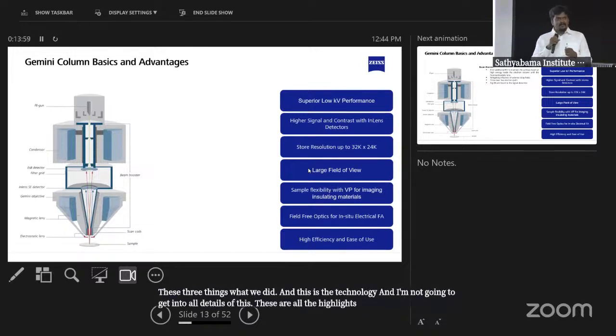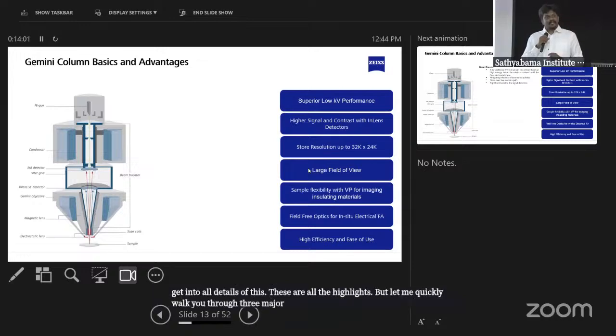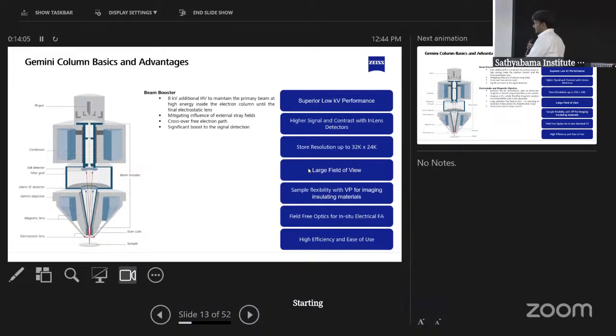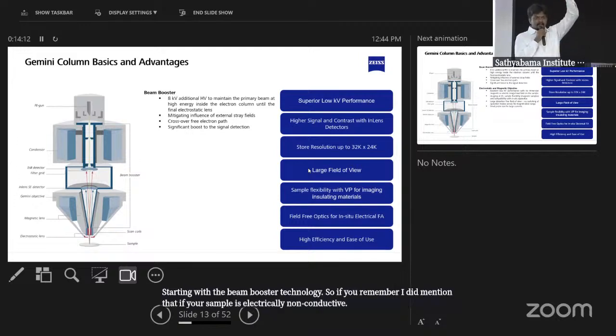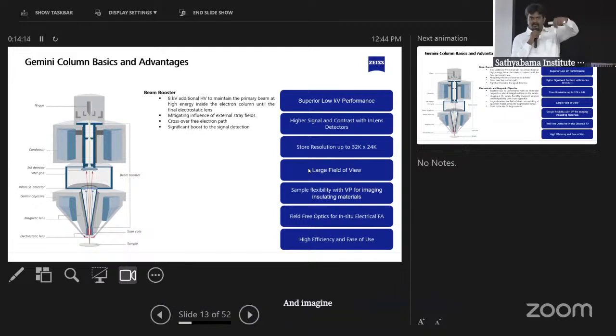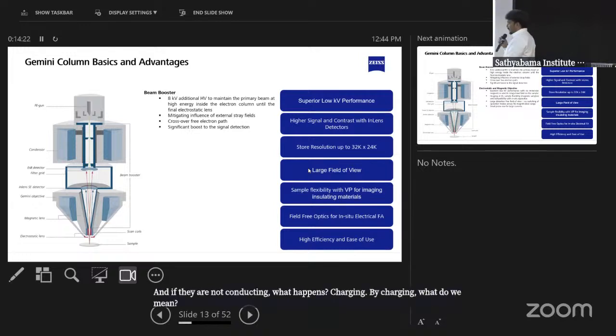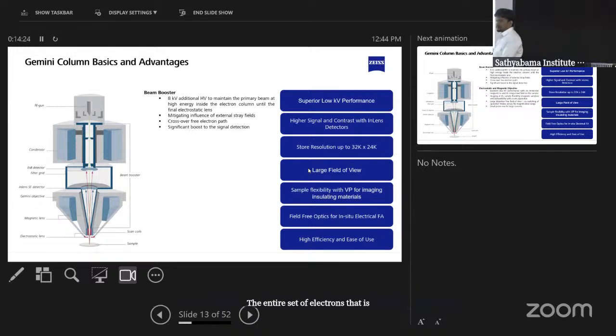But let me quickly walk you through three major uniquenesses of this technology, starting with the beam booster technology. If you remember, I mentioned that if your sample is electrically non-conductive, and imagine current is coming and falling on your sample, and it is not conducting, what happens? Charging. By charging, what do we mean? The electrons that are coming and falling on the sample surface start accumulating on the surface. So that's why you're not able to see anything.